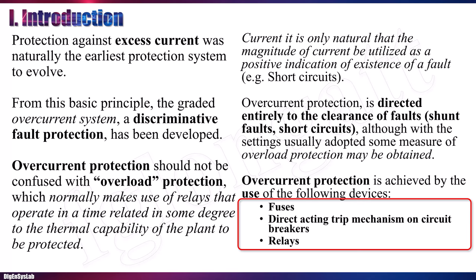During a short circuit or dangerous fault condition, the magnitude of the current can be several times the load current or nominal current. The overcurrent protection system uses the magnitude of the current as a mechanism to identify the normal and fault condition. We want to use overcurrent protection to minimize the exposure of the equipment and the potential danger to personnel by minimizing the effect of the overcurrent.